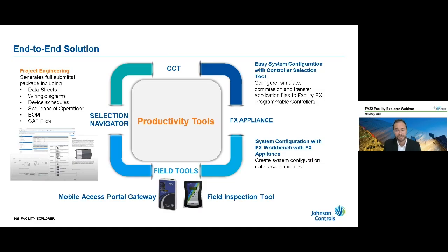Then in the commissioning phase, we use CCT, the controller configuration tool, to generate our field equipment controller applications, program and simulate the application logic, and generate the controller files, which are then imported into the FX appliance. You can easily and automatically build our supervisory database, including points and extensions, also generate our system graphics and automatically tag our systems.